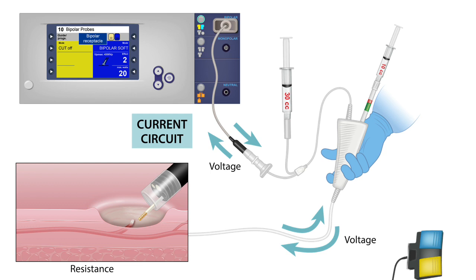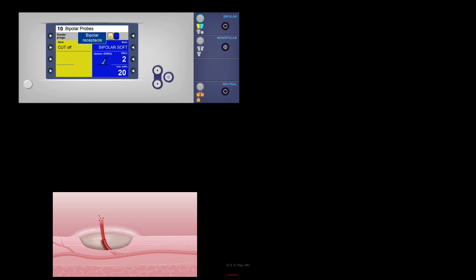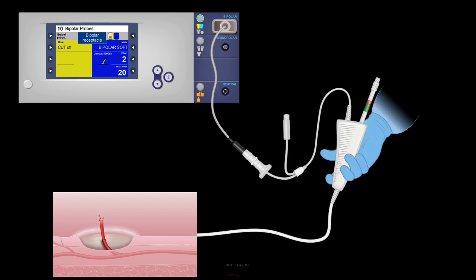So let us see how to set up. There are two ways to set up. One is you can use your electrosurgical unit that has a bipolar function as well, or you could use a dedicated machine with just a bipolar function. So let us see this. This is a patient who has a bleeding ulcer, and you have the bipolar setup that you picked on your machine here, and you attach the probe cord to the bipolar socket, not to the monopolar socket. It has to go to the bipolar socket, and then hook it up to the bipolar device. And then you can activate and create the coagulation effect.